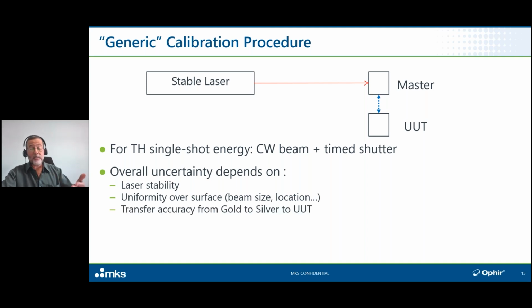The transfer accuracy from the gold to the silver to the sensor being calibrated. To a certain extent we do have automation in the process, but at the end of the day, there's human beings, very highly skilled technicians, but still human beings that are performing this calibration process overall, and there is a certain uncertainty that's still there. Linearity with power: we calibrated at 100 watts. How sure are we that that calibration still holds at 150 watts? We have to quantify all these things, which we do.